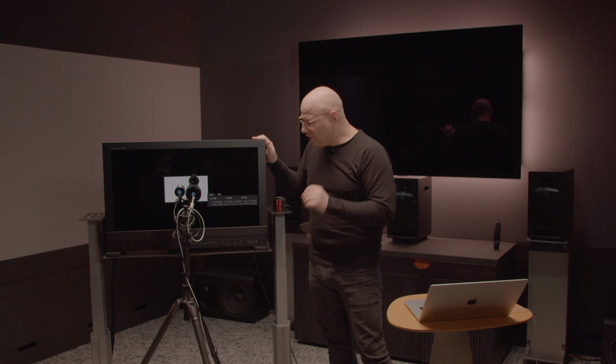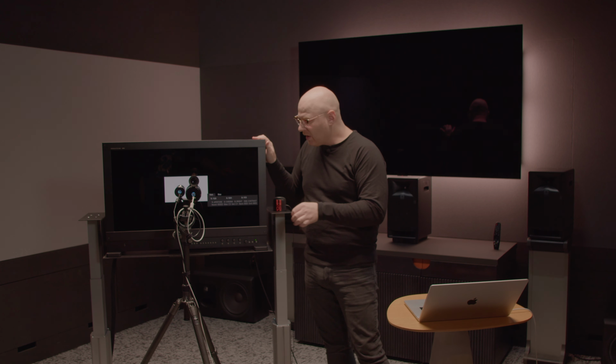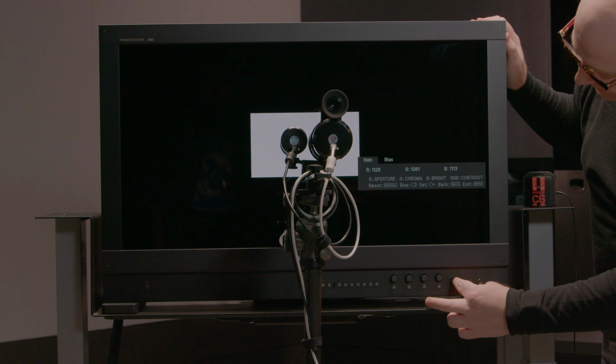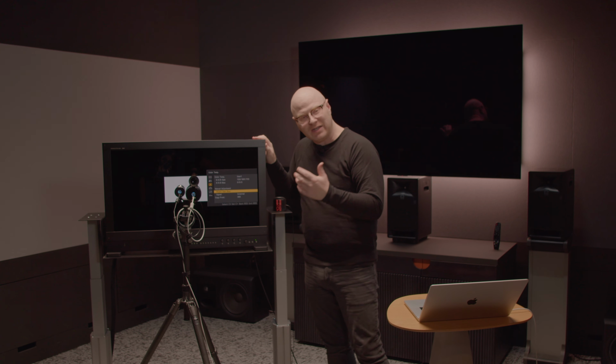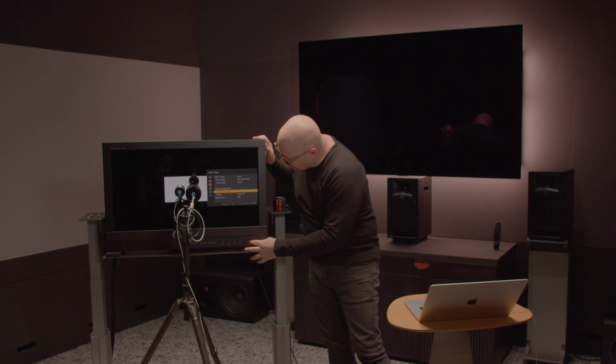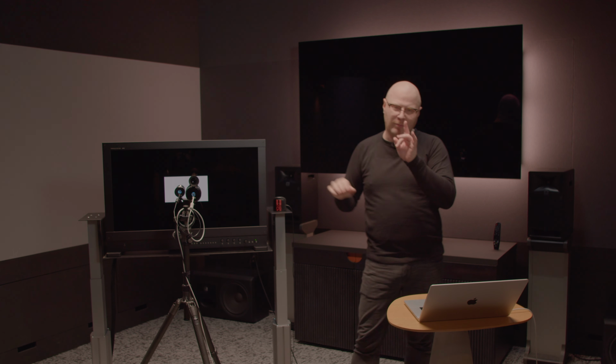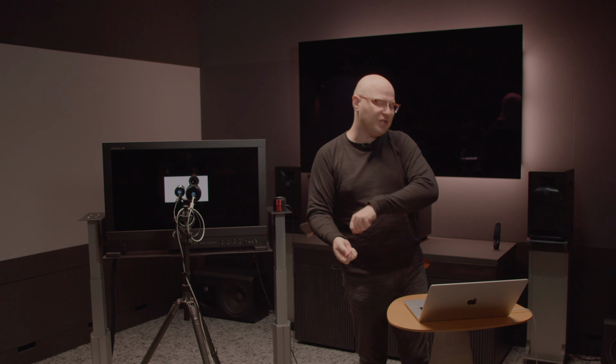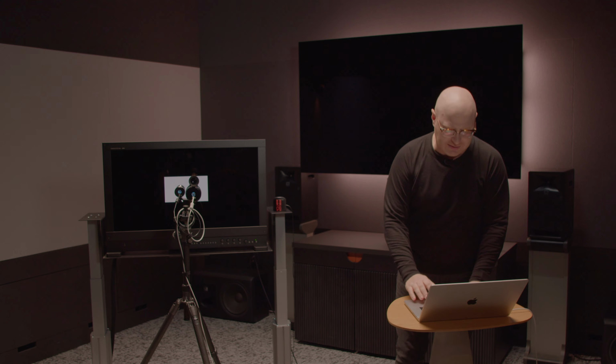A very important thing to note with the Sony BVM-HX310, once you're done making your adjustment, make sure you press the select enter button to save. You press it, it'll exit you out, and then you can hit menu or back to get out of the menu. If you don't press select enter and you press the back button, it's going to reset the controls to when you went into the menu. So if you do find yourself getting into trouble and needing to reset the display, just back right out without hitting that select enter button.